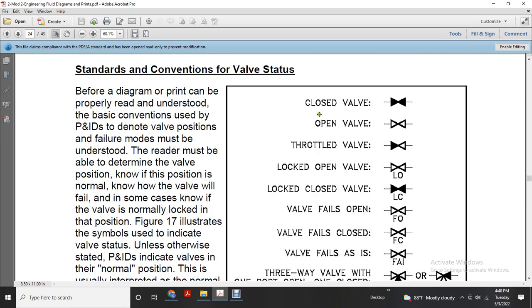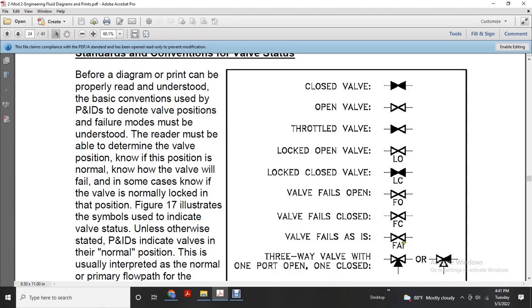A closed valve is shown with a fully filled gate valve, and an open one with a not fully filled symbol. Then a throttle valve symbol is a half-filled butterfly valve. Locked open is an empty, non-filled LO butterfly valve. Lock closed is a filled-in butterfly valve, LC. A valve that fails open is a plain butterfly valve, FO. Fail closed is FC. Fail as is is FAI. Then a 3-way valve with one port open and one closed.